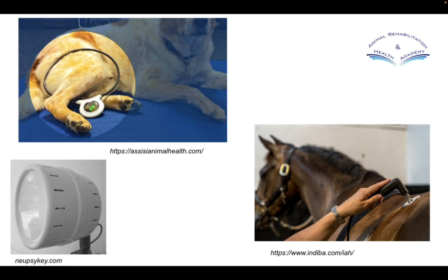And what that means is that you have a return plate. Obviously there's a horse in this picture. For horses, the return plate is normally on the sternum. So you have a closed circuit and you have a return plate. So from the electrode that you use here to the return plate, there has to be a connection made. And what is quite exciting, especially with horses, is that we can get a deeper penetration into the tissues. So that's very exciting. But that monopolar treatment is quite unique to this type of radio frequency electrical current.